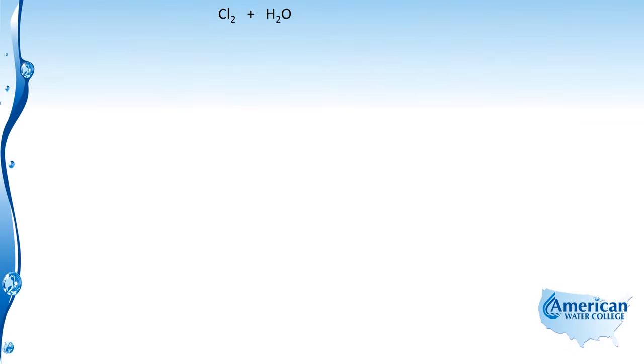When pure chlorine is added to pure water, it reacts to form hypochlorous acid and hydrochloric acid. Hypochlorous acid is one of the two forms of chlorine in a free chlorine residual. When the hypochlorous acid dissociates in water, it forms the other form of free chlorine, which is called the hypochlorite ion.